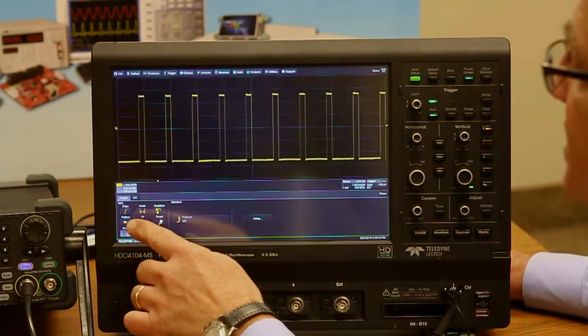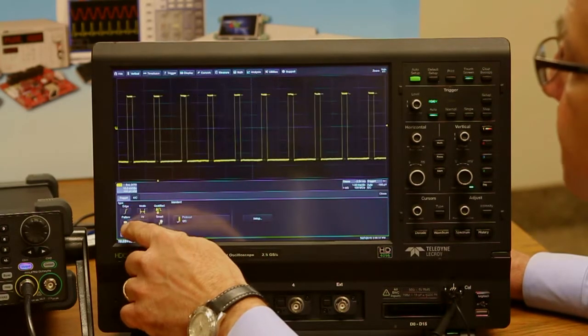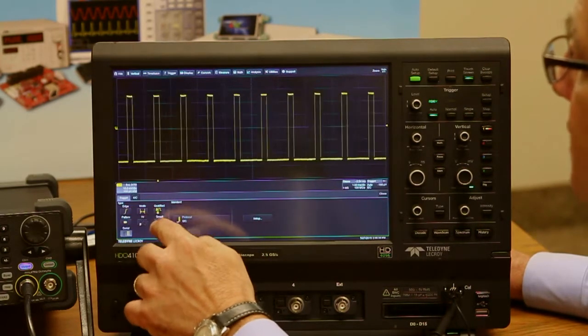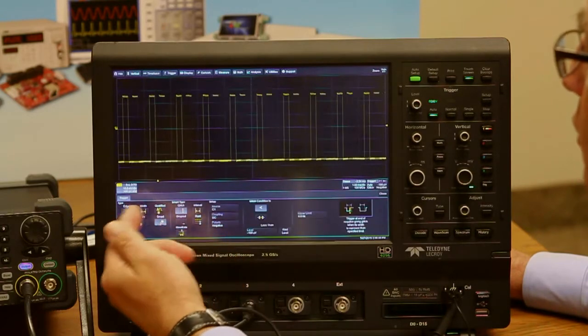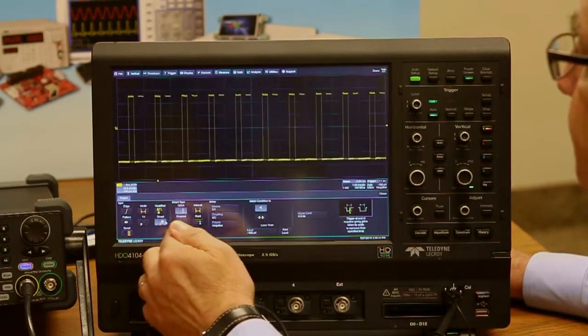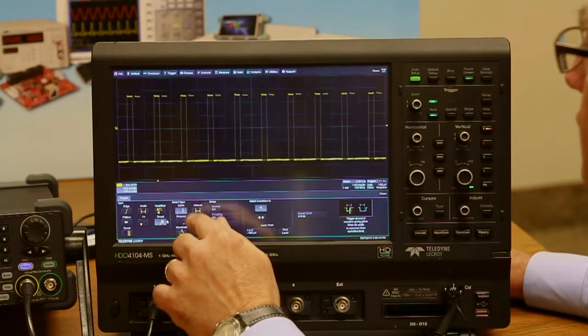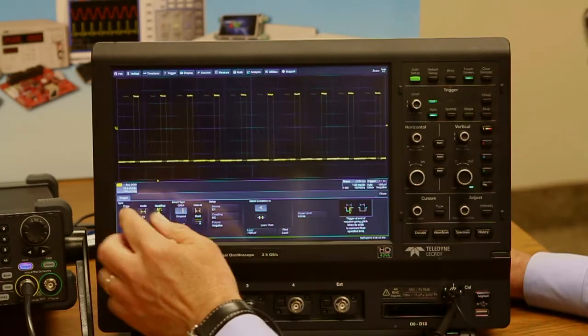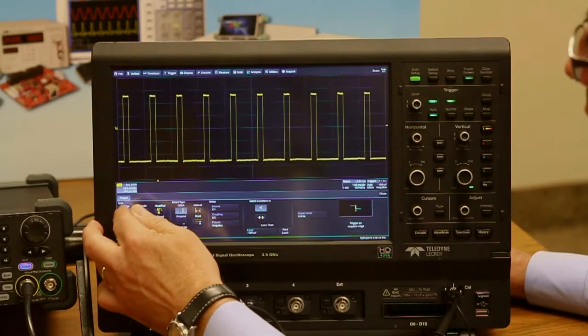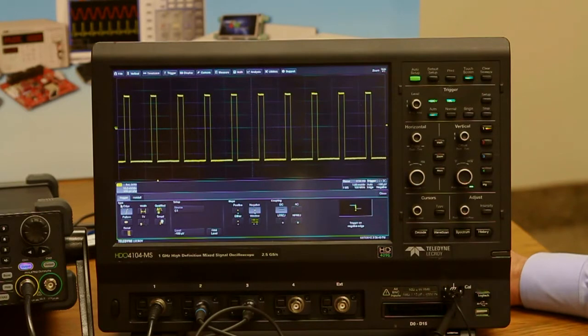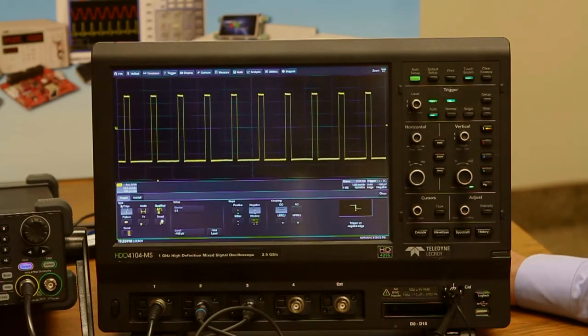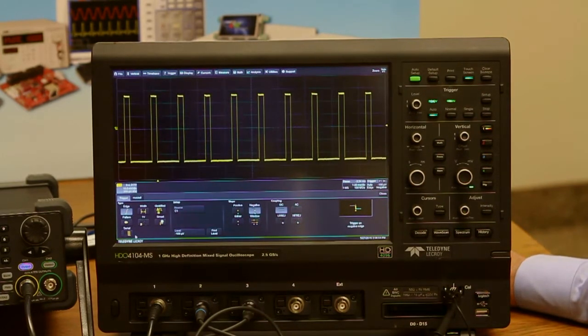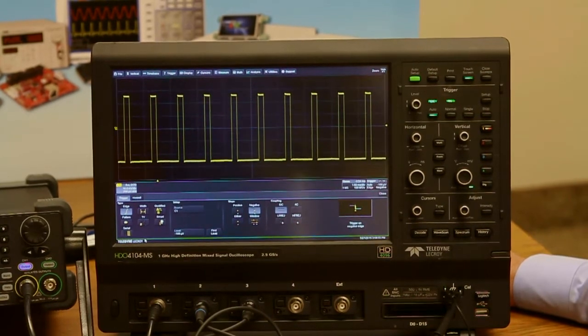Looking at serial or looking at smart triggers, you can also look at glitches and intervals and runts and dropouts or dV/dt, dI/dt, and how for example a MOSFET turns off and triggering within a range of certain values is all done in the trigger menu.